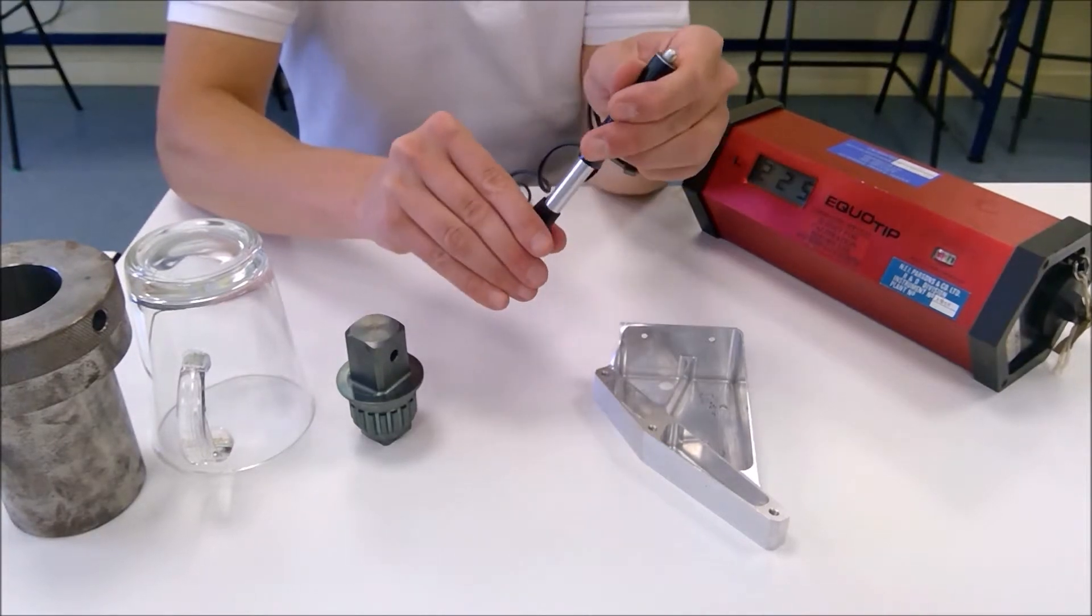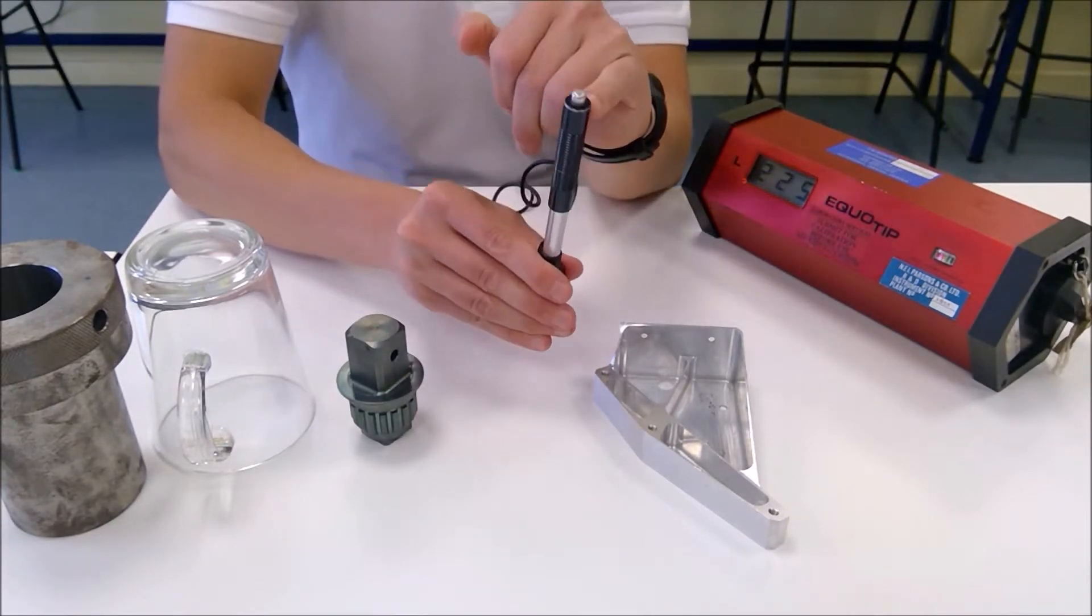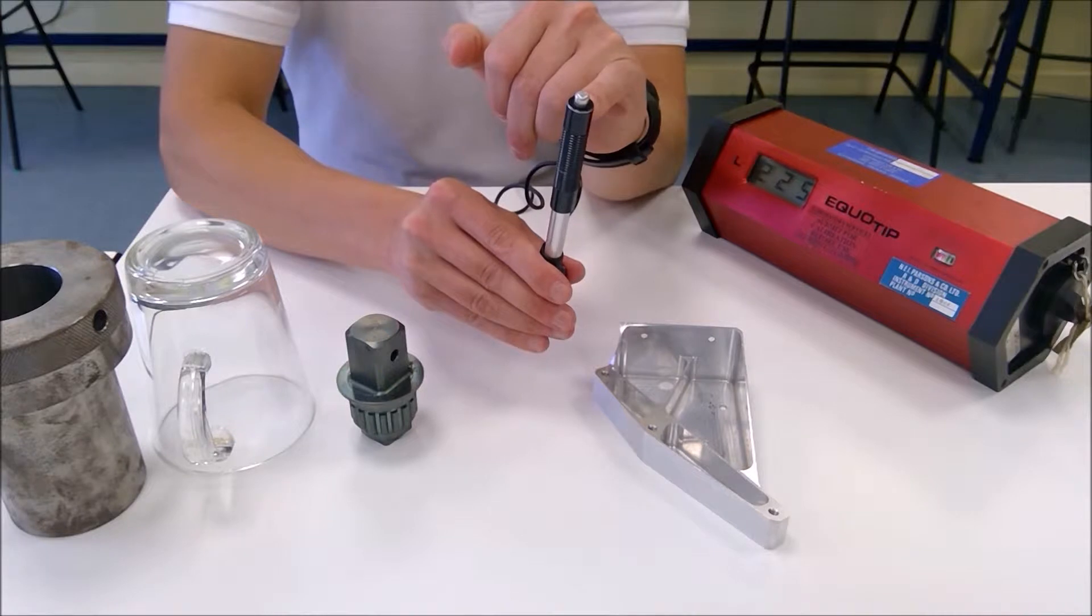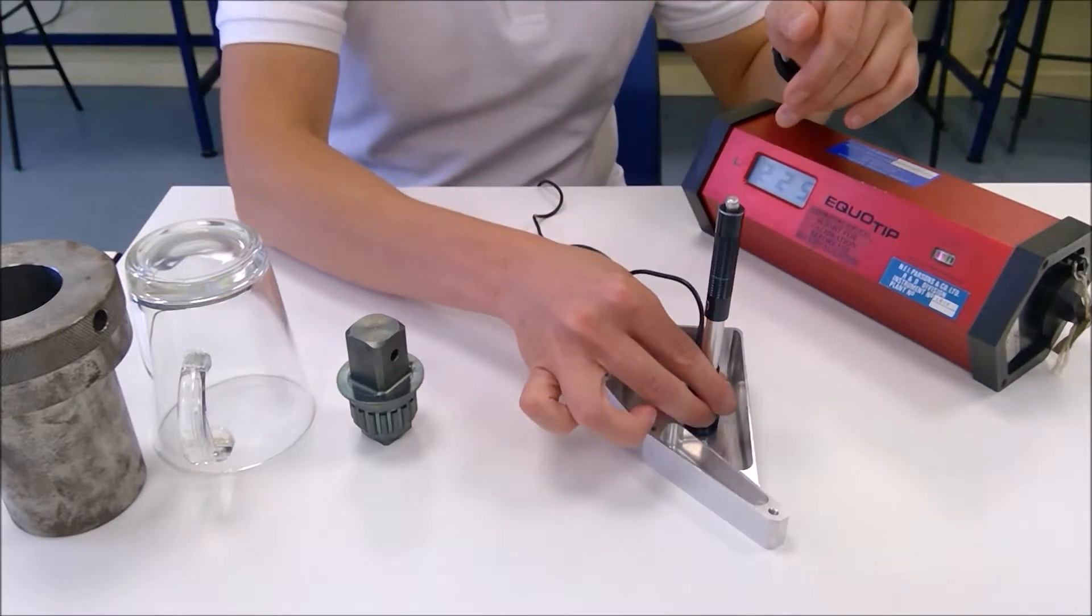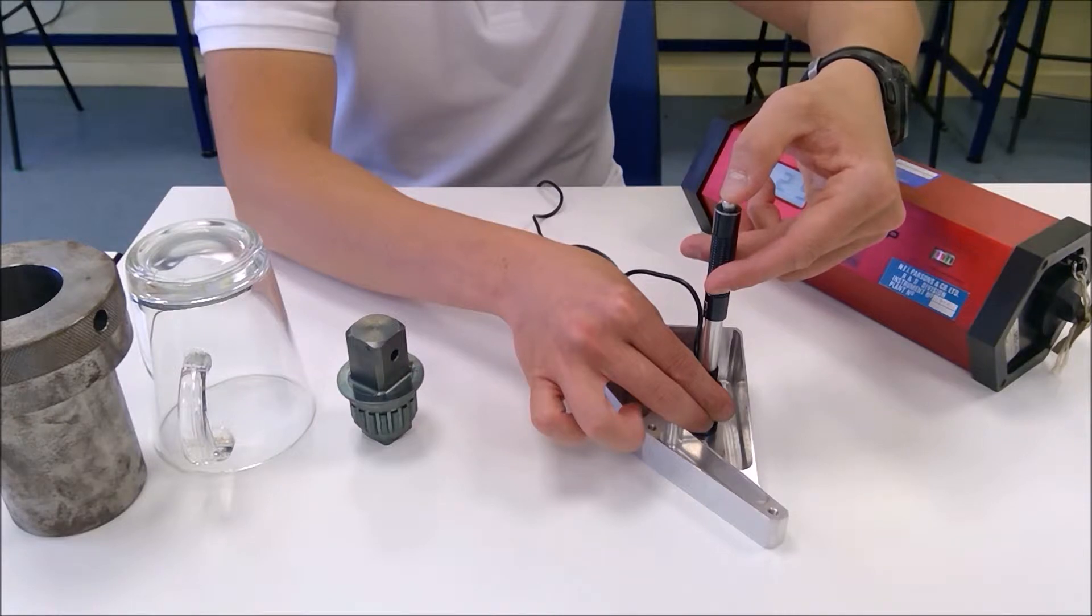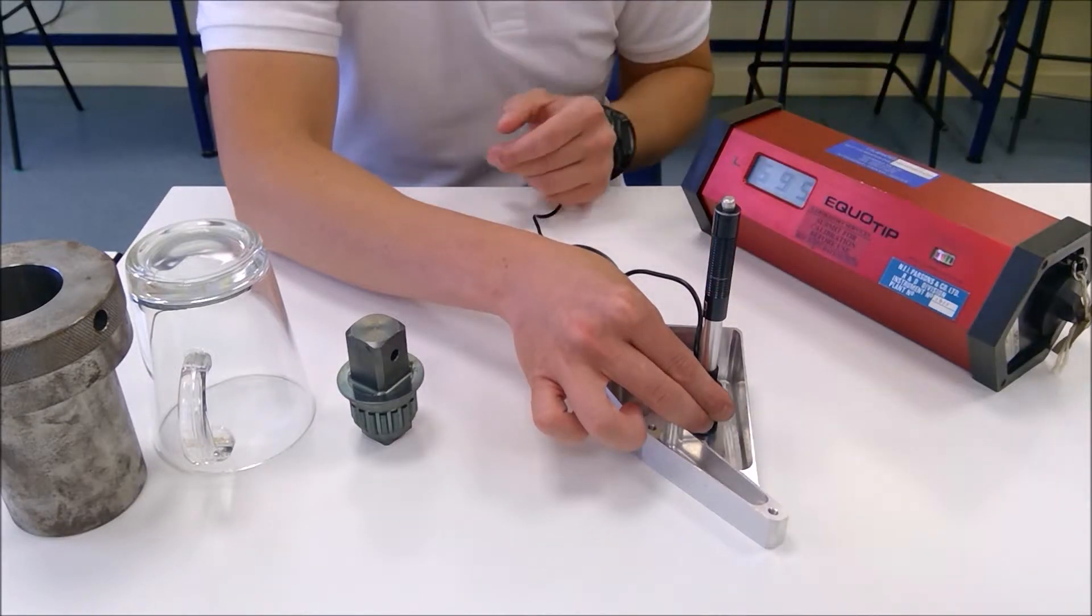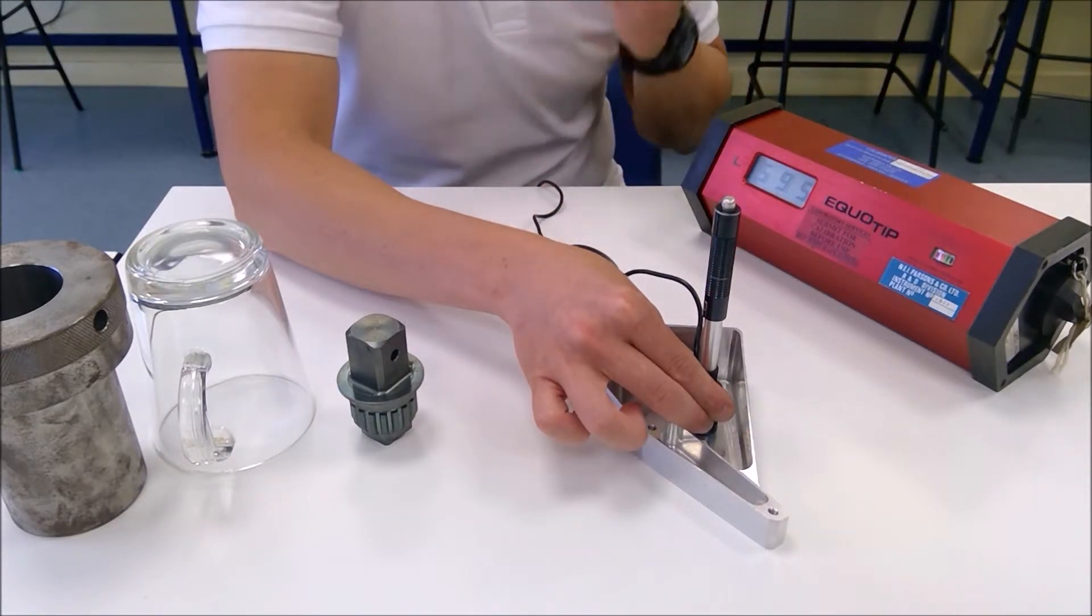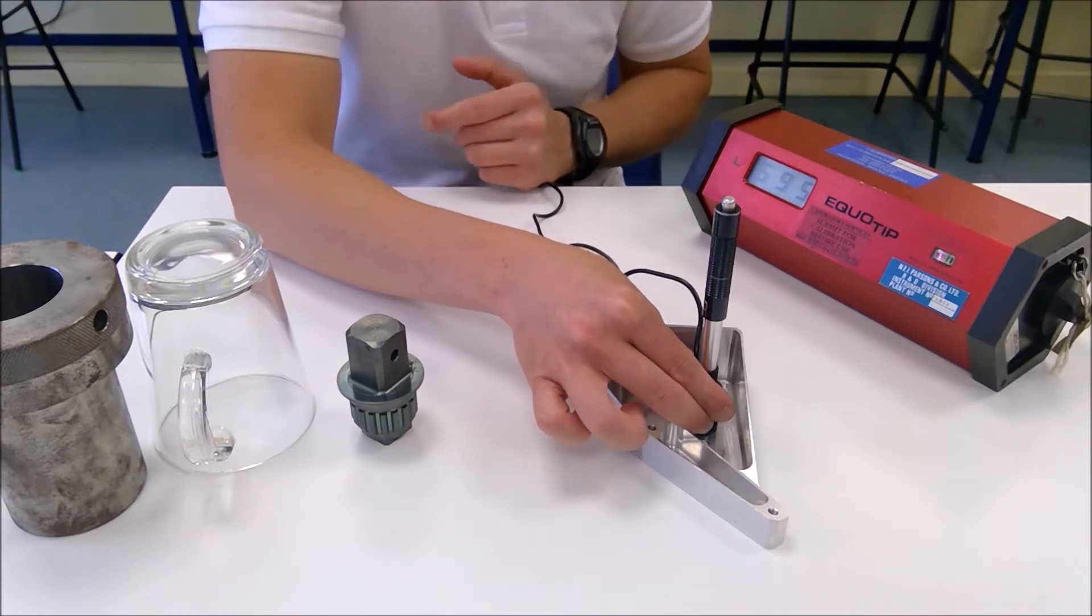So when we conduct the test we draw back the collar and that raises the pickup to the top of the probe here. We then position the probe on the surface that we're trying to measure and we press the button at the top to release the probe. You'll hear that the ball bearing strikes the surface and if you listen carefully you can actually hear it rebound.